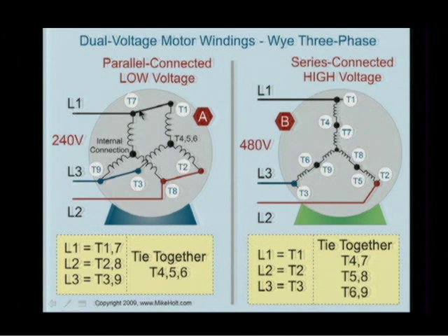No, I'm sorry. This is not 120. 240 divided by the square root of 3. Yeah, okay, we can't do it that way. It can't work out because you got the configuration different. But this is going to give us 2 windings at the higher voltage, and this gives me 1 winding at the lower voltage. So the windings are both going to get the same potential.